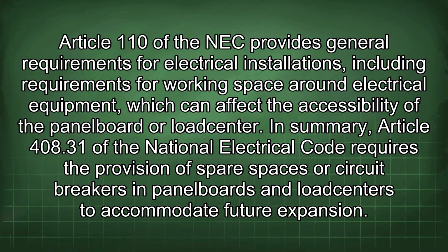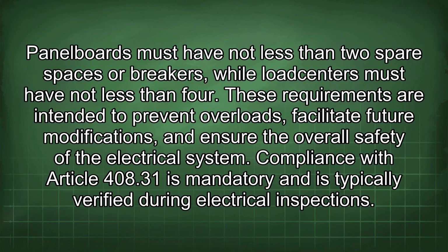In summary, Article 408.31 of the National Electrical Code requires the provision of spare spaces or circuit breakers in panel boards and load centers to accommodate future expansion. Panel boards must have not less than 2 spare spaces or breakers, while load centers must have not less than 4. These requirements are intended to prevent overloads, facilitate future modifications, and ensure the overall safety of the electrical system.